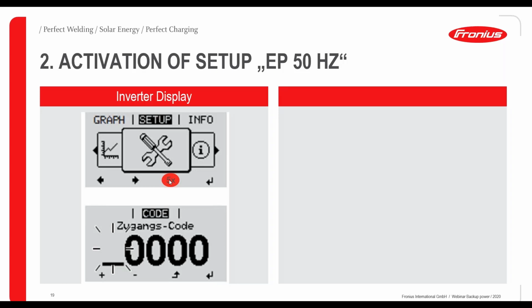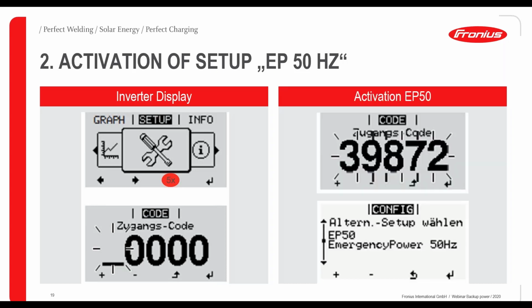Therefore, press the second button from the right hand side 5 times in a short period after another. Then you will see the code, a 5-digit code, which needs to be entered, and that's 39872. So just select these numbers with the plus minus buttons and then enter again twice, and then you come to the emergency power, to this selection of the different setups, and here select EP50 emergency power 50 Hertz. Theoretically, you could also select EP60 Hertz in a 60 Hertz installation when you have 60 Hertz in your country. And then if you have chosen this, you confirm that, and it's done. Then the setup will be reloaded. After a minute, the inverter will restart.